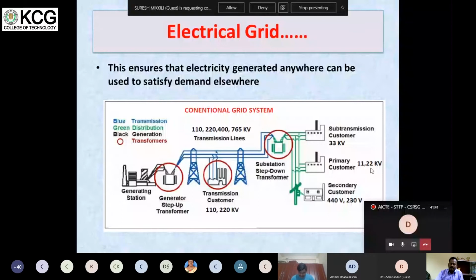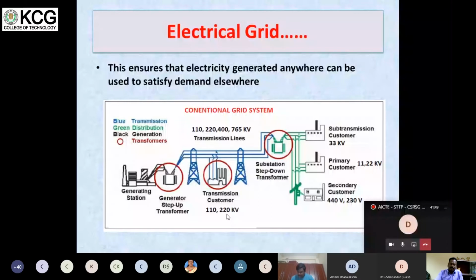And primary, 11 kV, 22 kV, is called LT industry, HT industries. And we have some consumers, transmission consumers like steel plants or cement plants, who take power from 110 kV or 220 kV. The main reason is that when they take power from 220 kV or 110 kV, the disturbance will be less. If there is any problem at the consumer end, only the primary side or primary switchgear area will be shut down, and the transmission line will not be disturbed. So that is the reason some heavy power consuming companies take supply from the transmission system at 110 kV, 220 kV. Railways also take power from 110 kV, 220 kV. And 11 kV, 22 kV are the primary consumers, HT industries, who take power from the grid.